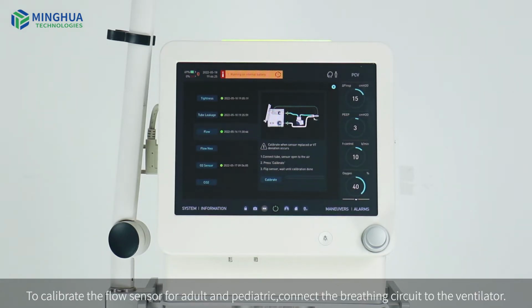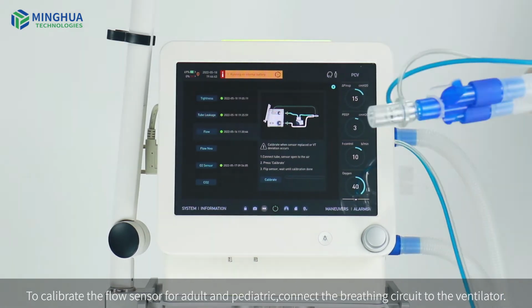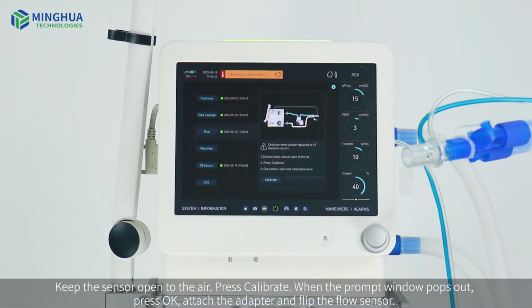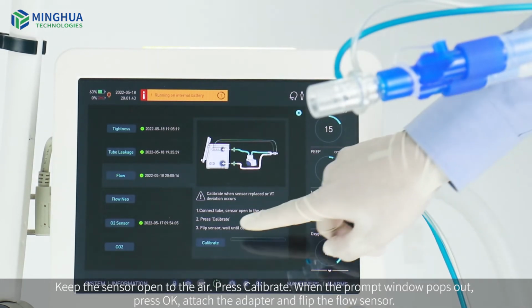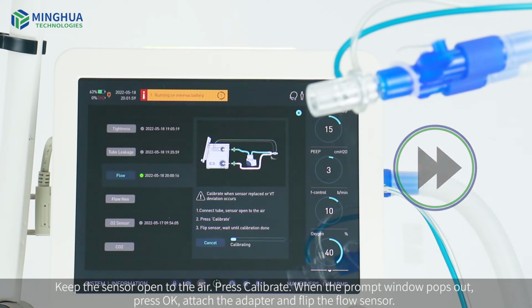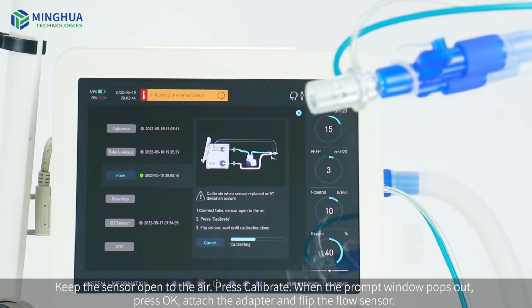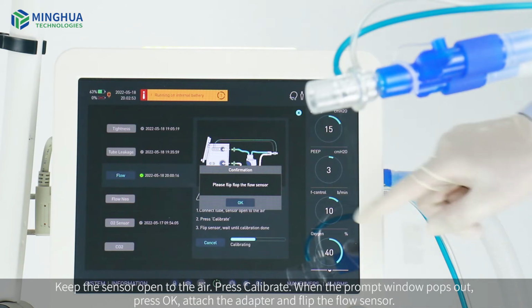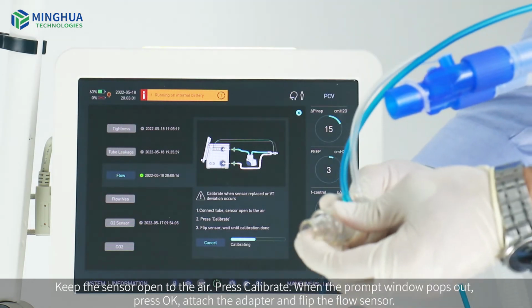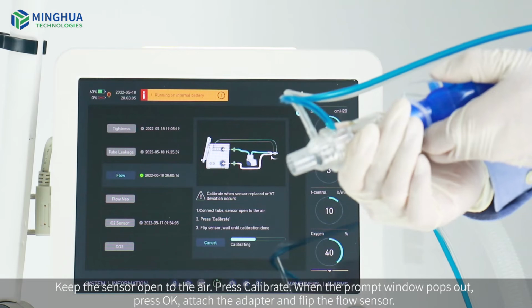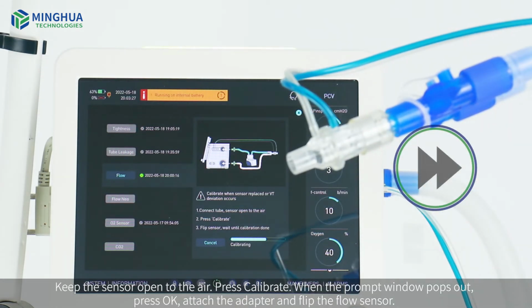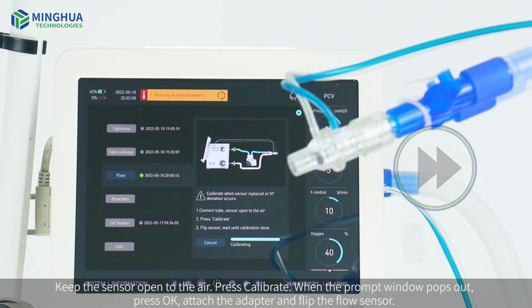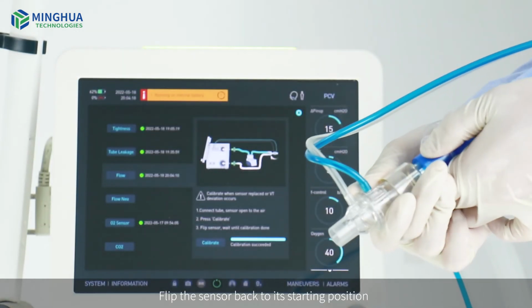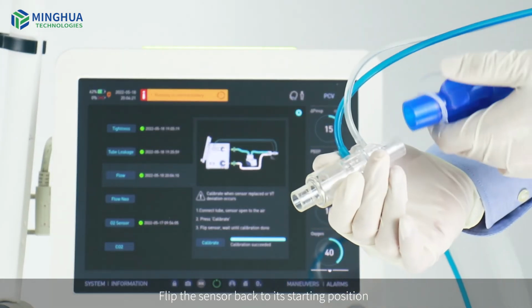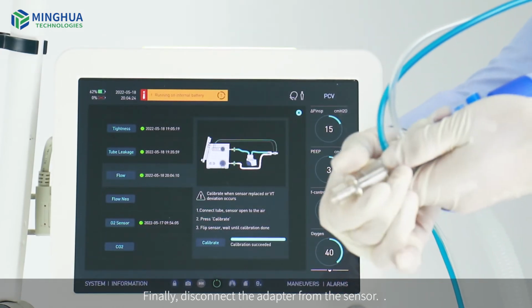To calibrate the flow sensor for adult and pediatric, connect the breathing circuit to the ventilator. Keep the sensor open to the air. Press Calibrate. When the prompt window pops out, press OK. Attach the adapter and flip the flow sensor. Flip the sensor back to its starting position. Finally, disconnect the adapter from the sensor.